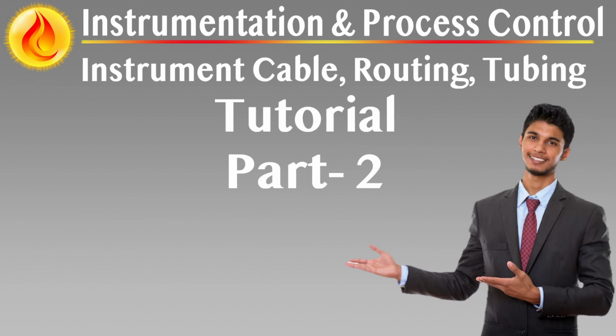Routing must prioritize low fire risk zones and avoid congested or high temperature areas. Above ground installations are acceptable with principal approval where cost savings or local standards justify their use. Underground routing offers better fire and impact protection and should be used where practical. Design must accommodate 10 to 15% spare capacity in all multi-core tubing installations to allow for future instrumentation upgrades or reconfiguration. Any pneumatic lines serving emergency shutdown, depressurizing, or fire protection systems must be routed and protected with the same rigor as electric safety-related cabling, ensuring performance during fire or seismic events.